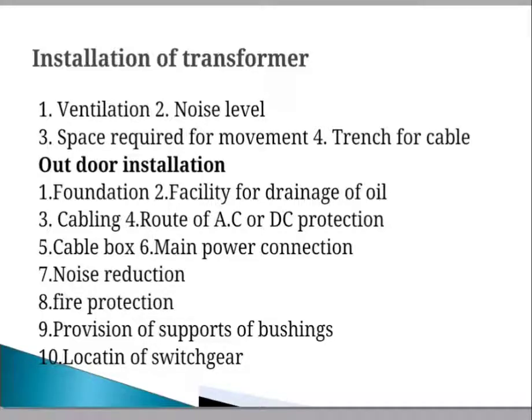The next point is the facility for drainage of oil. For transformers having an oil capacity of more than 9000 liters, we have to provide a proper drainage facility. For transformers installed outdoors where the oil capacity is more than 9000 liters, proper drainage of oil is very important.